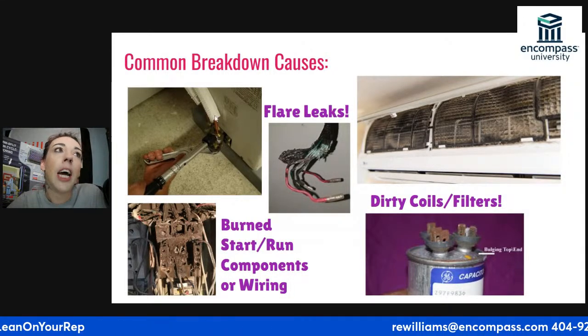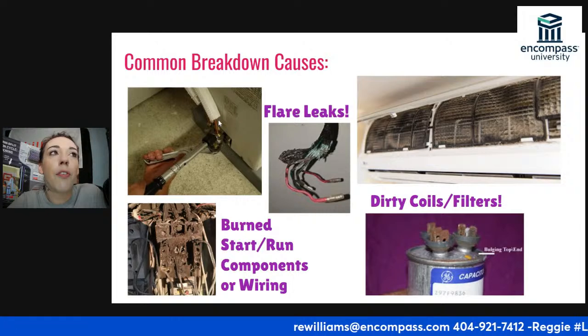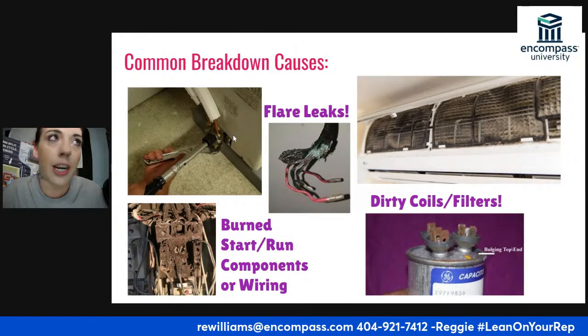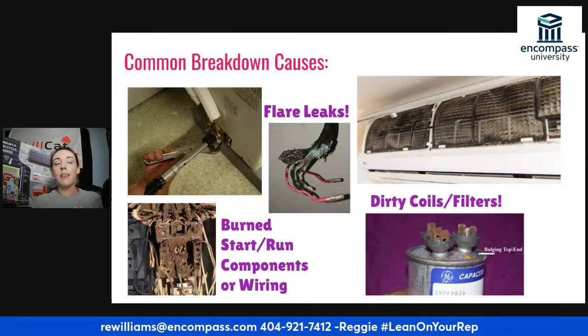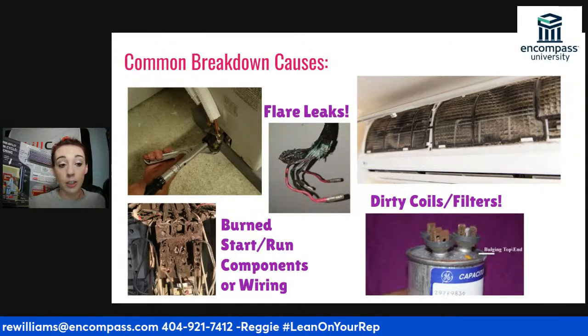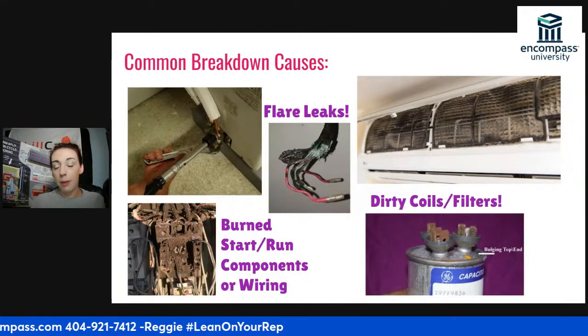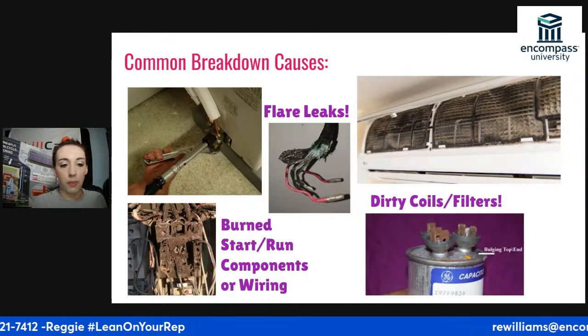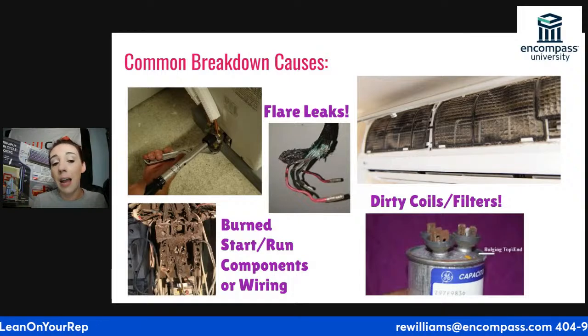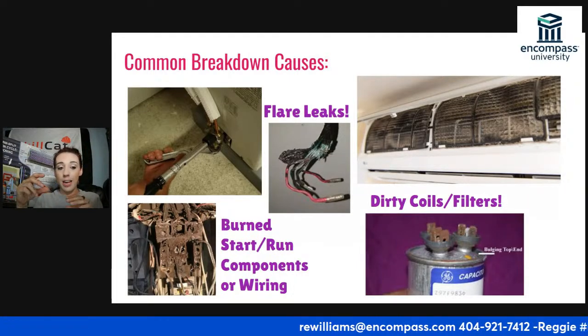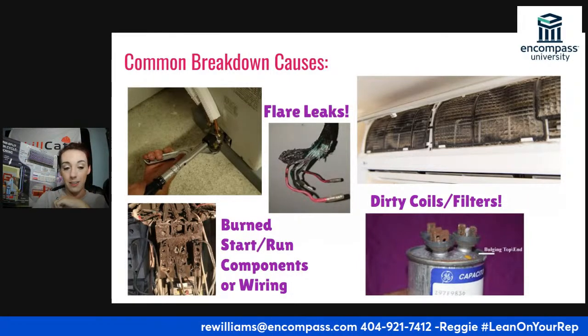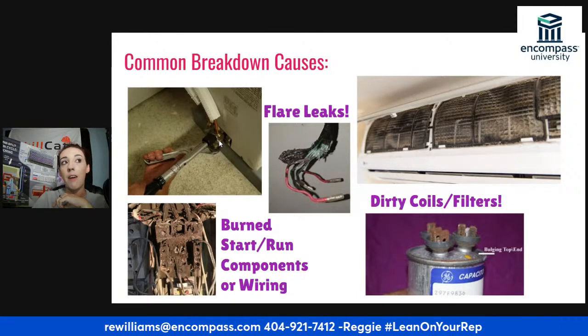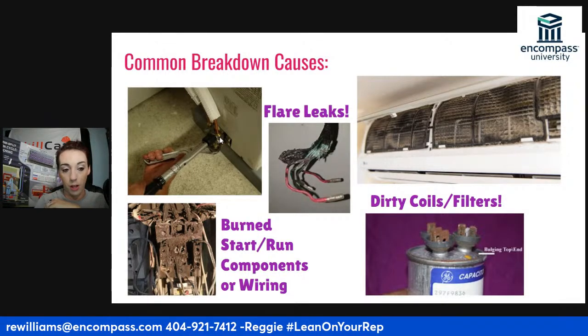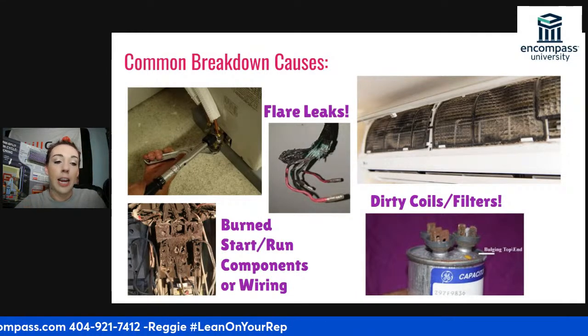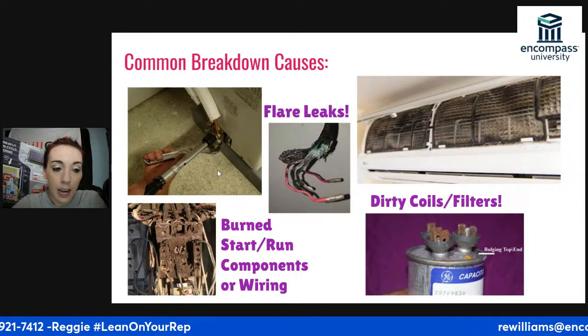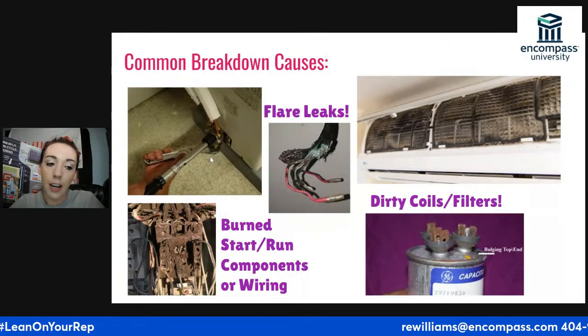I kind of want to get into something else in this picture, but first let's get into the flares. So when you get a line set from your supplier or distributor, a lot of the time it just comes with a flare nut, but a lot of the times it will have the flare nut on it and it will have what looks like a flare at the end of the pipe to keep that flare nut onto the pipe, so it doesn't fall off. If you're getting that from the manufacturer that way, that is not a flare connection.